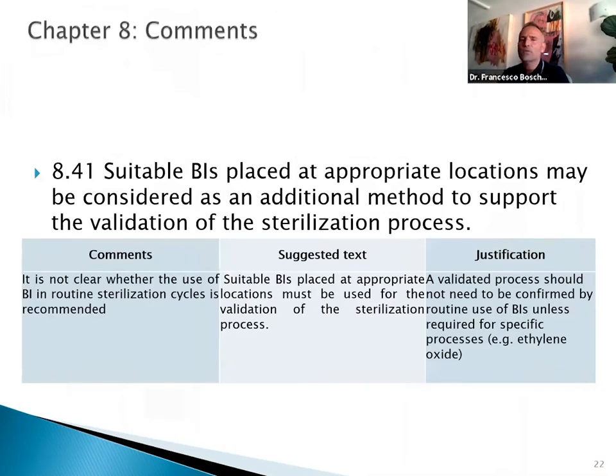Our comments were referred, for example, to point 8.41, which is a little bit ambiguous because it says that suitable BIs placed at appropriate locations should be considered as an additional method to support the validation of the sterilization process. So for us, it's not clear whether the use of BI in routine sterilization cycles is recommended. But if this is the case, we think that a validated process should not need to be confirmed every time with BIs, which is the meaning of validation.